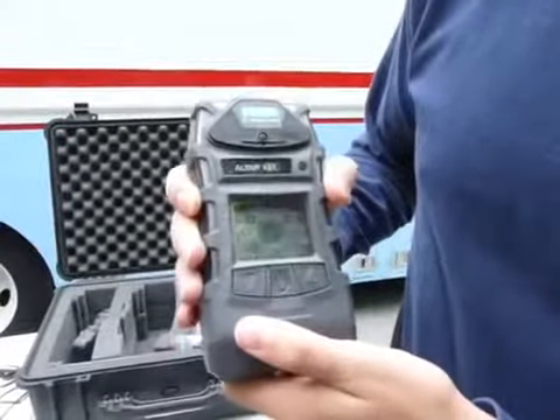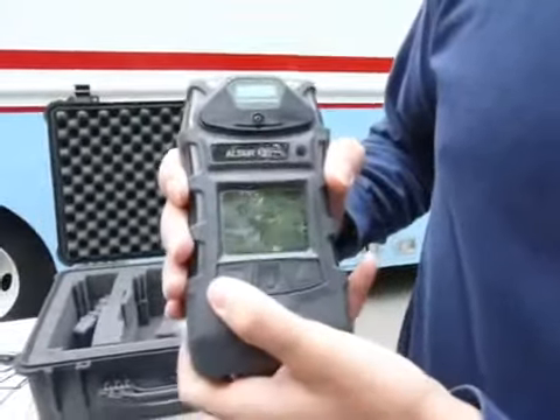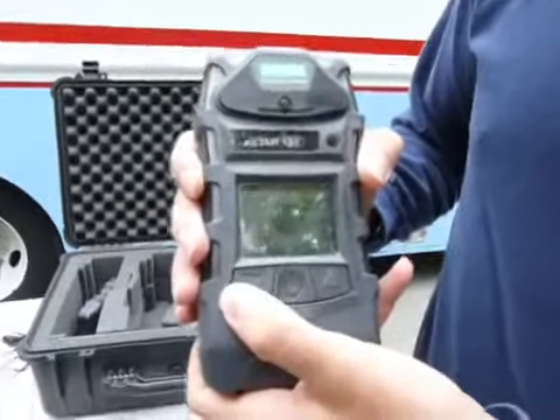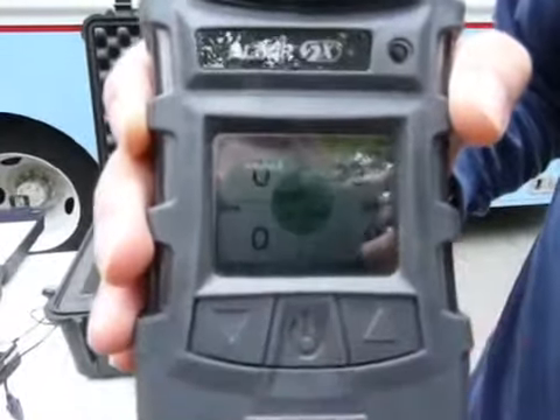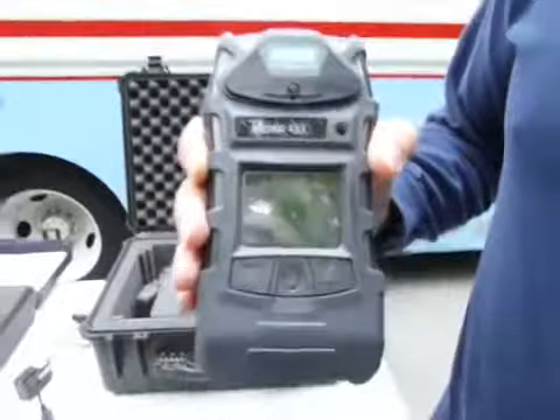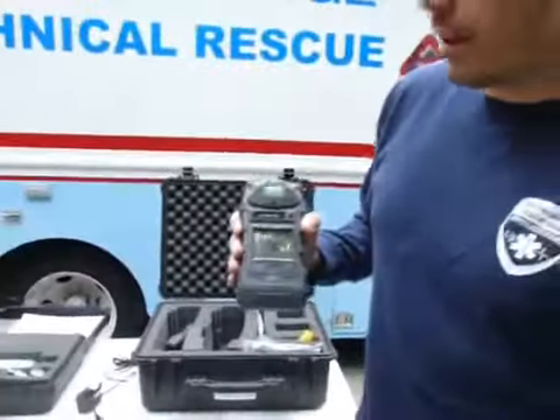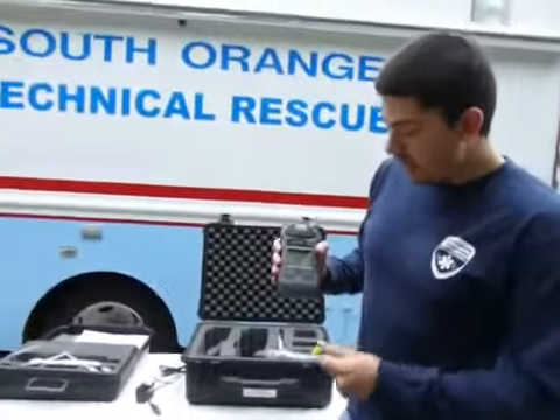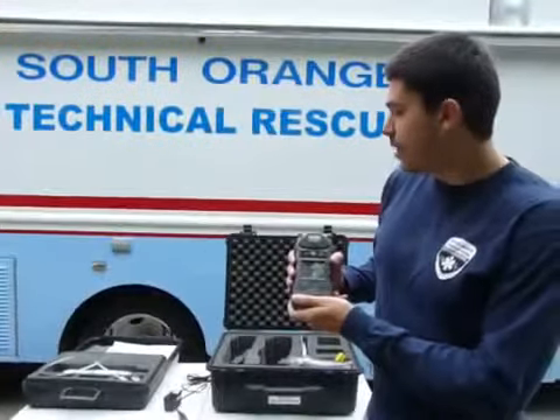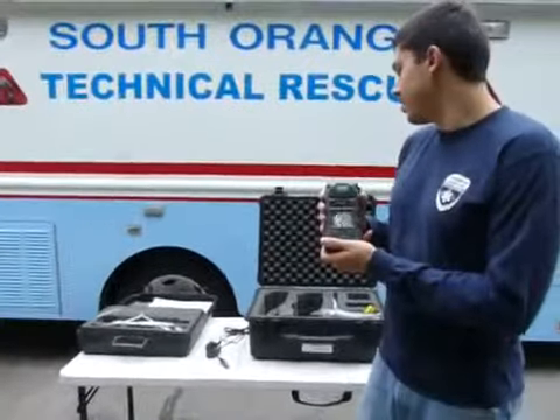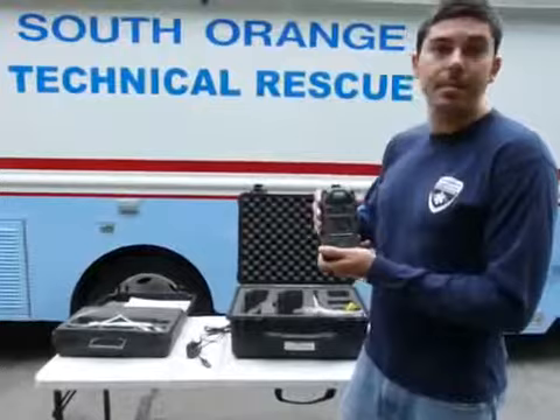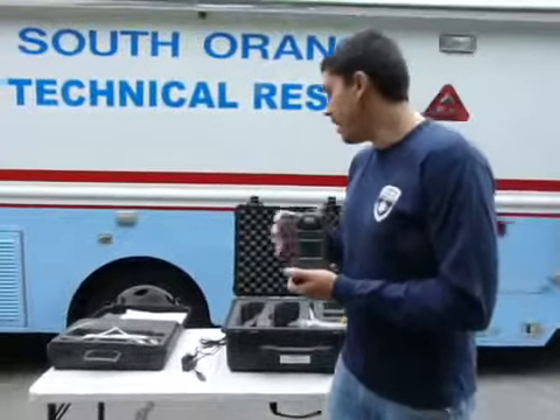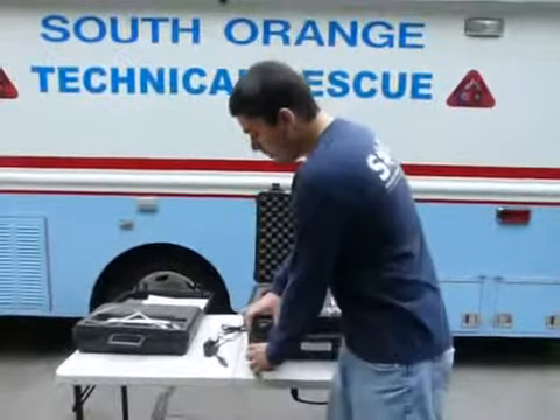Another important thing when we first turn this monitor on is to quickly do a bump. A bump is basically where we feed a little bit of calibration gas into the monitor to let it check that the sensors are working properly. So to do that, what we're going to need to do is actually grab the calibration gas, set it up, and connect it to the monitor. So I'm going to put the monitor down for a second.